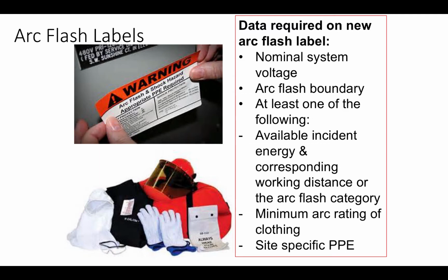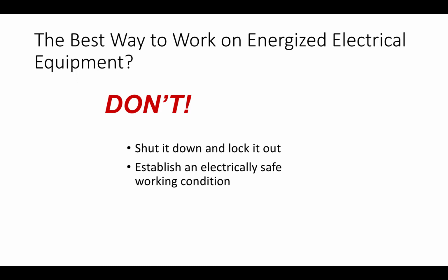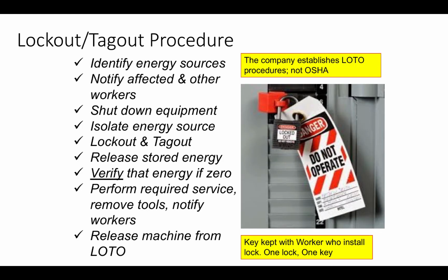Labels are required. They must contain the nominal system voltage, the arc flash boundary, and at least one of the following: available incident energy and corresponding working distance, or the arc flash category. You have to have the minimum arc rating of the clothing, and you have to have site-specific personal protective equipment. The best way to work on energized electrical equipment: don't. Shut it down and lock it out. You want to establish an electrically safe working condition.